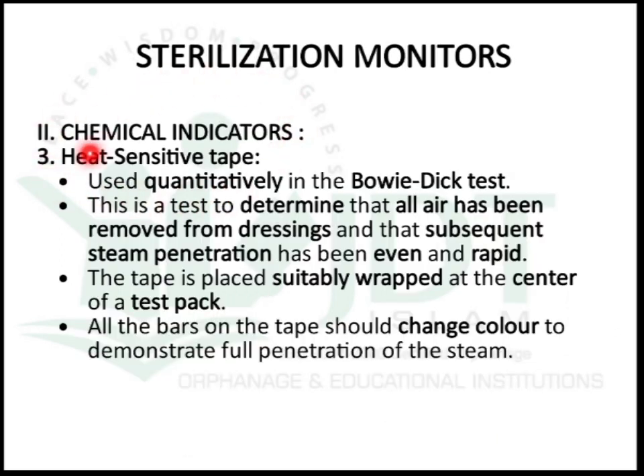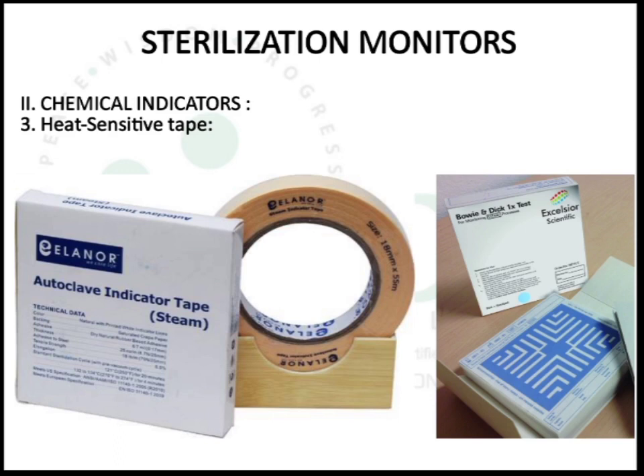Heat-sensitive tape is used as a chemical indicator, used quantitatively in the Bowie-Dick test to determine that all air has been removed from the dressing and that subsequent steam penetration has been even and rapid. The tape is placed suitably wrapped at the center of a test pack, and after sterilization all the bars on the tape should change color to demonstrate full penetration of steam.